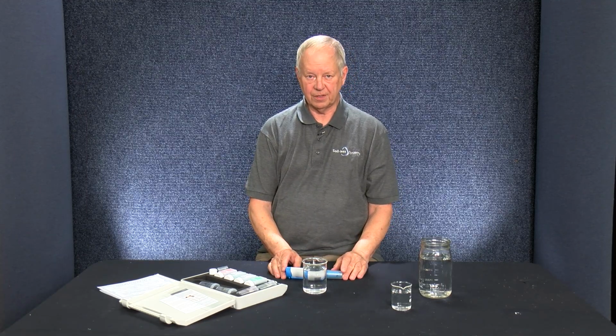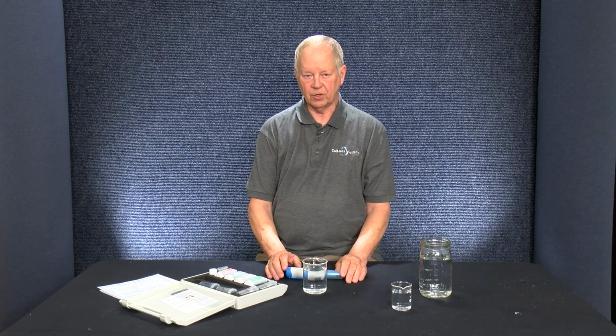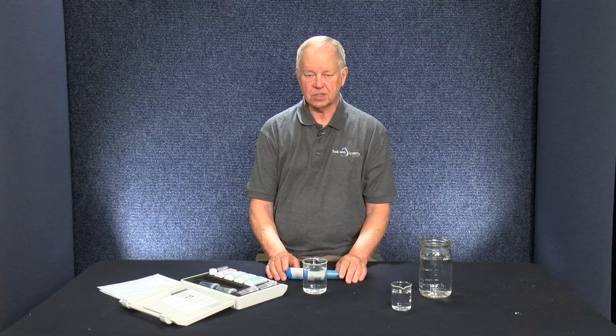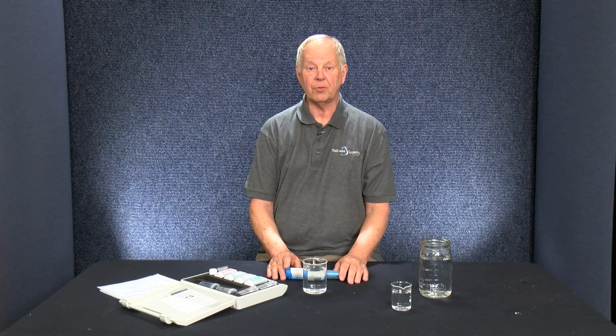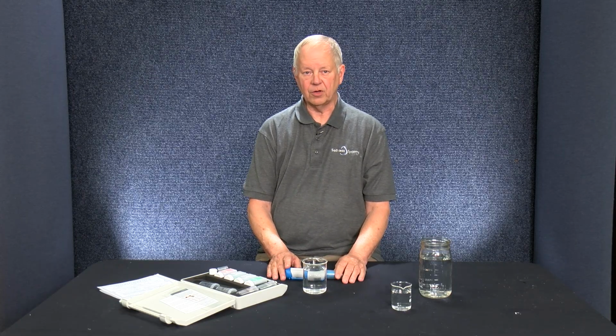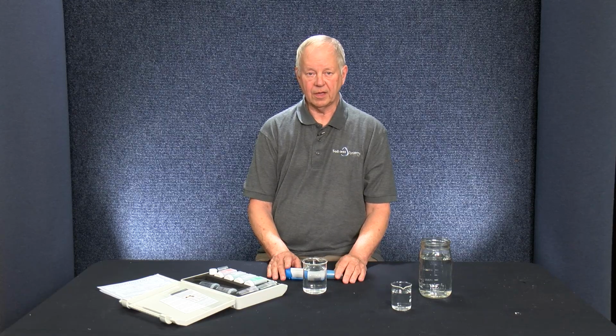Periodically, you need to calibrate your meter. This particular meter, we're going to use a 2-point calibration starting at a 7.0 pH and then a 4 pH. You can calibrate it up to the 10.01 pH. We don't have that sample here, but we're very rarely going to be over 7.0 in pH to measure, so we only need to have an accurate range. Then after that, we're going to calibrate the EC probe, the salinity probe. Our salinity calibration can actually be pretty high. In our case, we're going to go with the 1413 because that's in the range of all our nutrient blends.